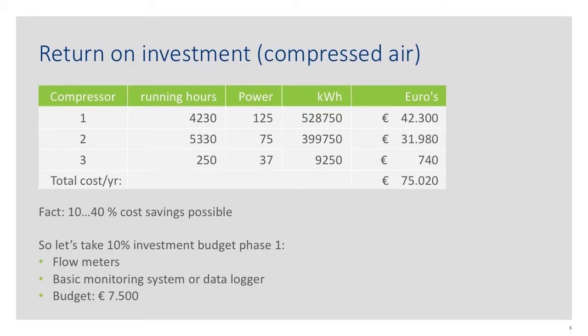Another example of that, so how we calculate return on investment. Basically, this is an example of a 3-compressor system. So if you know the running hours, if you know the rated power, you can calculate how much kWh they consume per year. And you can translate it into euros or dollars. For the sake of this example, well, there are euros in this example, but it doesn't really matter. So if you look at the total amount and you take a very conservative 10%, you would spend around 7.5K in a monitoring system or in a couple of flow sensors, a couple of kW meters to check what is actually going on. That amount can be gained again in savings quite rapidly.